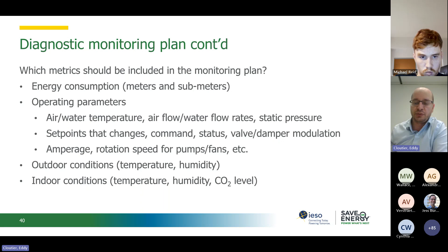So regardless of the format, the diagnostic monitoring plan will generally always include basically the same information and will help guide the commissioning team to implement the required measurement. Who will implement the metering really depends on the client's internal capabilities, the capabilities also of the building management system, and the desired objectives. The first element, there is obviously the objective, or what we want to check on the mechanical or electrical system.